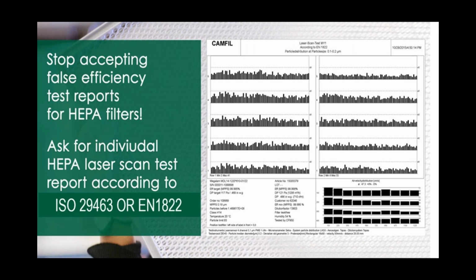Every HEPA filter should be tested in the factory. It should have an individual test certificate. That certificate should give you a range of particle sizes and its efficiency at those particle sizes. It should have details like the airflow, the efficiency, the test environment, the temperature it was tested at, and the humidity in the environment, etc. It should have a unique serial number, and it should be traceable back to the manufacturer and the plant that it was manufactured in. So if you're going to start using air cleaners, request that these air cleaners have the correct HEPA filter. And I'm not saying it has to be a Camfil HEPA, but a HEPA tested according to EN 1822 or ISO 29463.